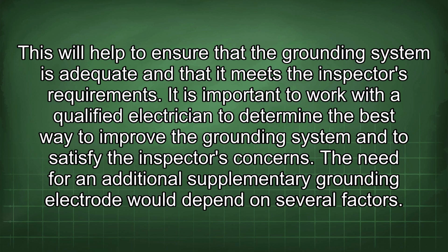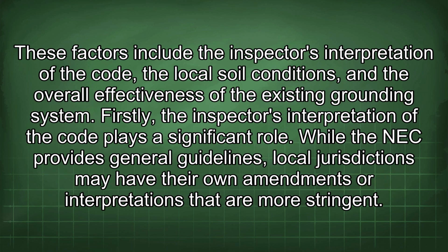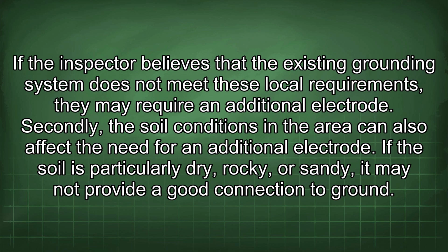The need for an additional supplementary grounding electrode would depend on several factors. These factors include the inspector's interpretation of the code, the local soil conditions, and the overall effectiveness of the existing grounding system. Firstly, the inspector's interpretation of the code plays a significant role. While the NEC provides general guidelines, local jurisdictions may have their own amendments or interpretations that are more stringent. If the inspector believes that the existing grounding system does not meet these local requirements, they may require an additional electrode.